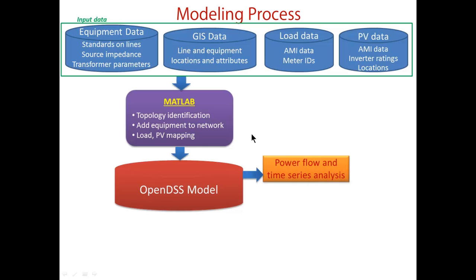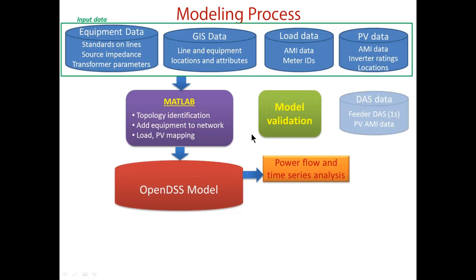So OpenDSS is used to run multiple power flow and time series analyses to study, for example, the impact of different PV levels on the voltage profile of the feeder, or the losses in the feeder, and so on. Now these results are also compared with the measured DAS data under similar scenarios, and together they are used to validate the model that we developed. And if there are discrepancies, that gives feedback to the MATLAB engine to make adjustments to refine the model, so that the analysis results completely match the field measurements.